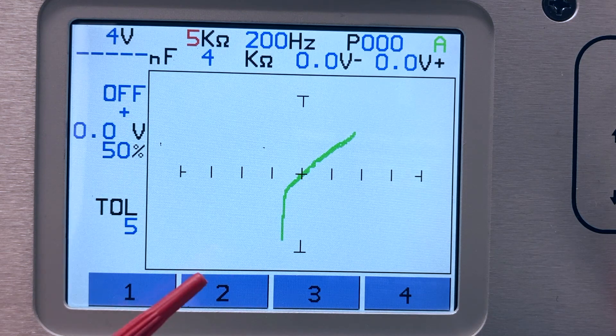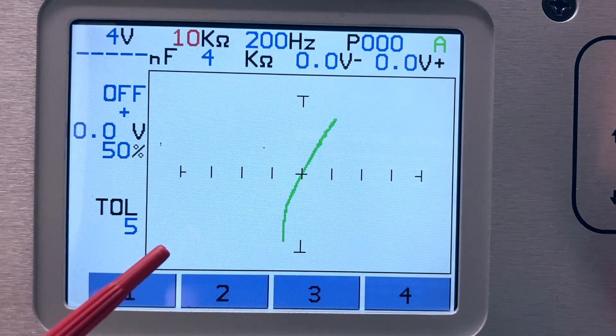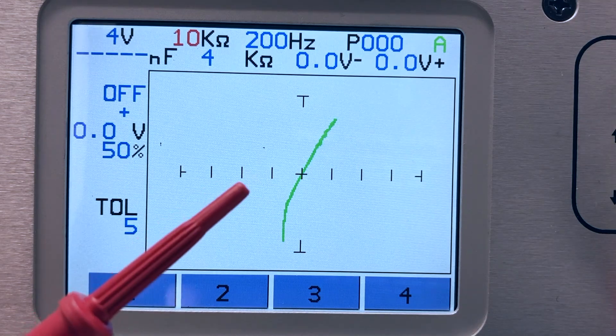You never know how resistive a failure will be, so using a 10k to 50k ohm range will ensure you do not miss high resistance failures.